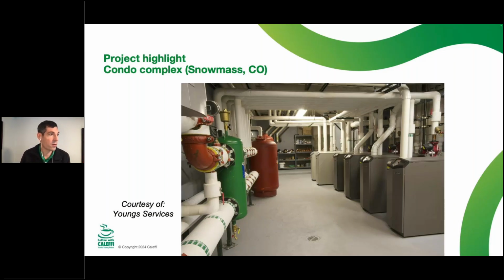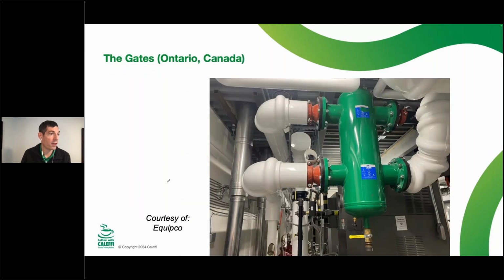Got 4 different system pumps, got 2 different ECM pumps. They are separated from left to right here with that separator, and that's exactly what we're trying to do on a much more complicated commercial scale. Same thing with multiple boilers here going out to a big building that our rep in Canada and Ontario, this project Equipco put together. Looks great, really small footprint, and we can take 90s right into this where we wouldn't be able to do that with closely spaced tees.